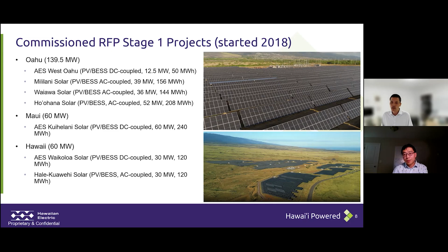In Stage 1, which started in 2018, those are all grid-following plants. In what we call Stage 2, which started in 2020, we did a procurement in 2018, and before those projects even got into the engineering phase we started another procurement round, which we call Stage 2. Around that study timeframe, we recognized that grid forming was coming out and was going to become something our system may require, because of the large amounts of inverter-based resources.